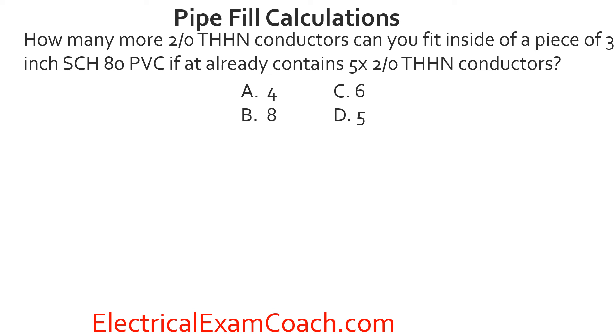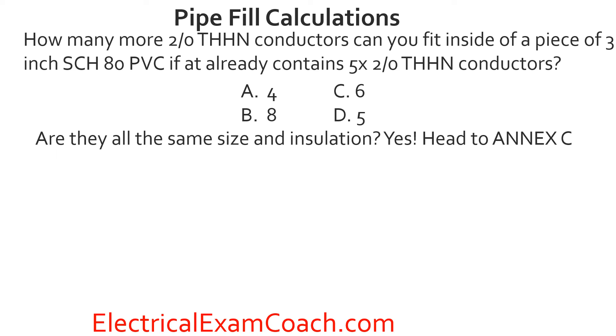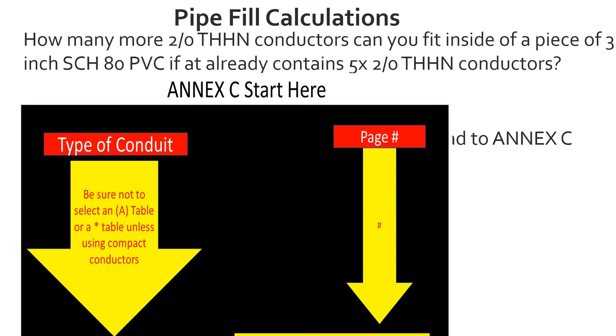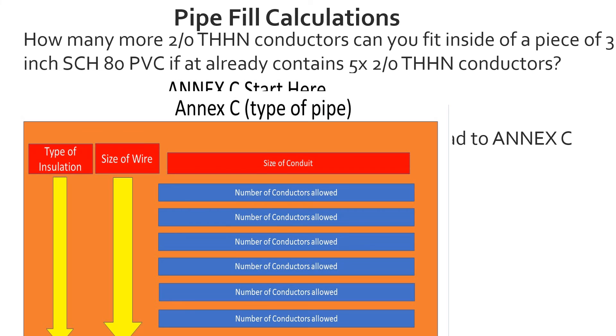Practice problem: How many more 2/0 THHN conductors can you fit inside a piece of 3-inch schedule 80 PVC that already contains five 2/0 THHN conductors? Are they all the same size and insulation? Yes. Head to Annex C, find schedule 80 PVC — not the A version — go to the page number, read the black bold heading, find THHN insulation, find 2/0 wire size, come across the top to 3-inch conduit, and tee off. The table shows 11 total. Minus the 5 already there, we can fit 6 more.